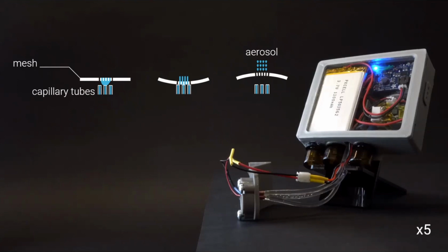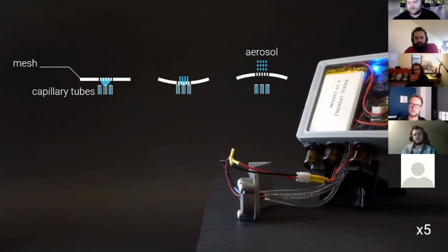What this ends up creating is a situation where a capillary tube can have a small droplet that's pushed out. It gets caught by the vibrating mesh transducer and then atomized, and other tubes won't be leaking out liquid at the same time. That's what the illustration is of.